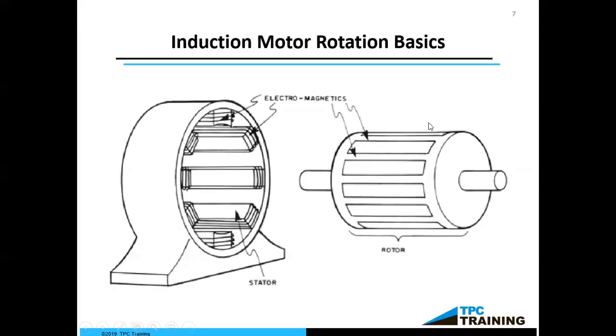Here we can see the two basic parts. We have our housing on the outside, but right inside that housing you can see our stator windings. Those are stationary, and they help us with the magnetic field. When we energize these windings, the magnetic field will tend to rotate all around. While it's doing that, we have to remember that it's getting larger and smaller, so it's moving, and it will induce another magnetic field in this rotor. Then as the magnetic field rotates around this stationary part, the magnetic field will bring this rotor right with it.